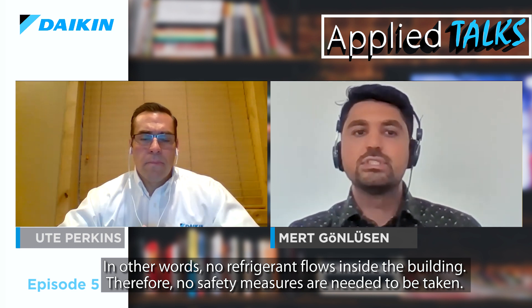That's fantastic. So next question — how do your customers accept this change? And what about the other refrigerants with low GWP within scroll compressor technology? Well, all the customers in our market are already very much familiar with R32, thanks to our long-existing DX portfolio with R32 refrigerants. It's very rare nowadays that we face questions about R32. Although rare, we are asked about the categorization of R32 and if it brings any additional constraints during the project design phase. R32 is an A2L refrigerant, which means it's mildly flammable compared to A1 refrigerants such as R410A. However, this doesn't really bring any additional constraints in the project, as our air-cooled R32 chillers or heat pumps are installed at open air, such as on the roof — meaning no refrigerant flows inside the building. Therefore, no safety measures need to be taken.